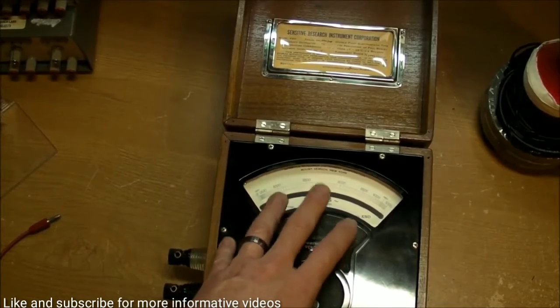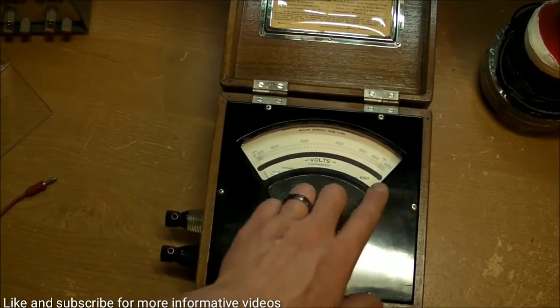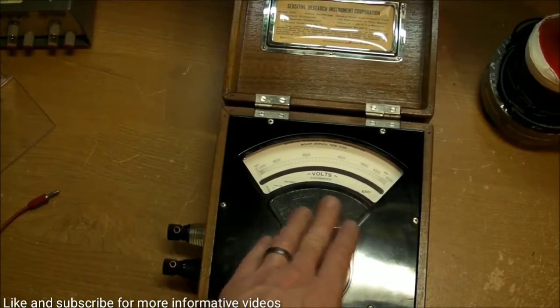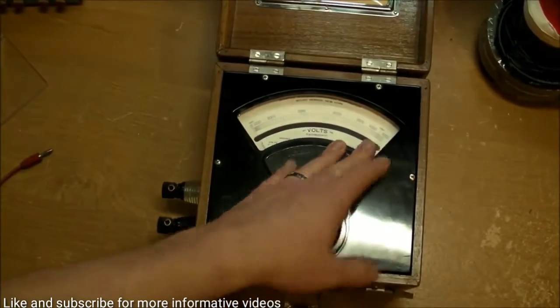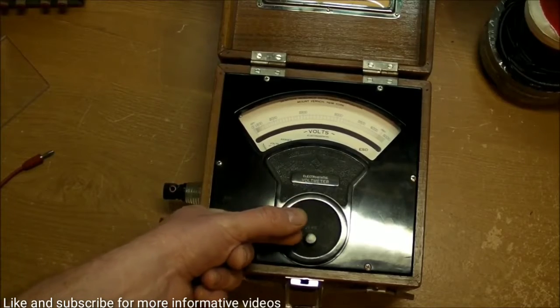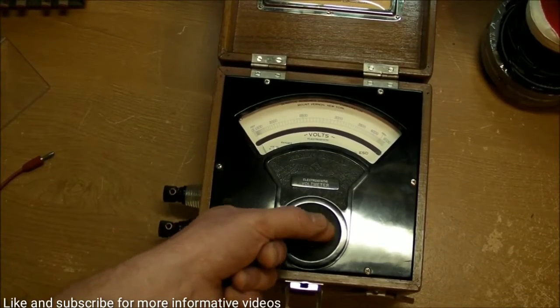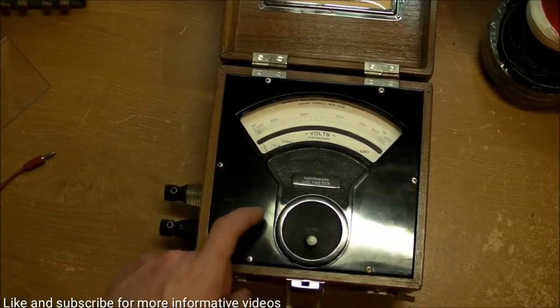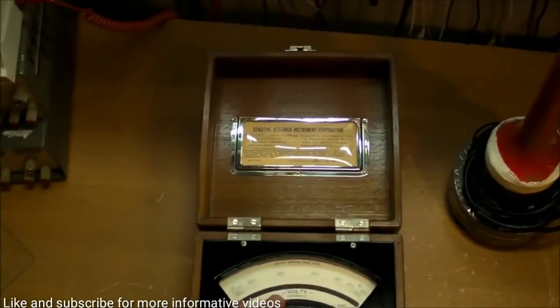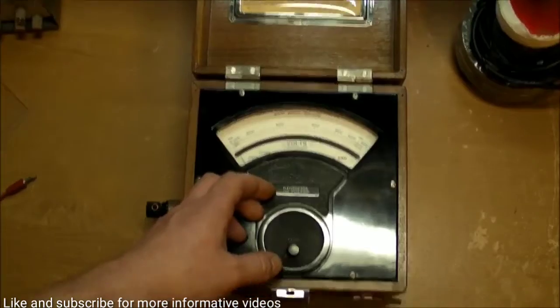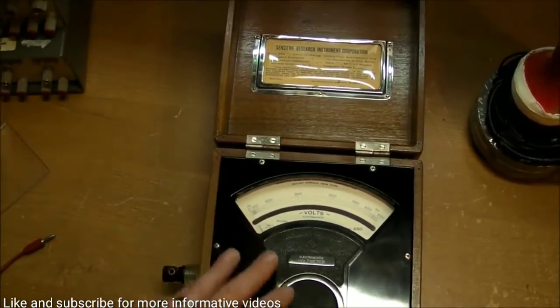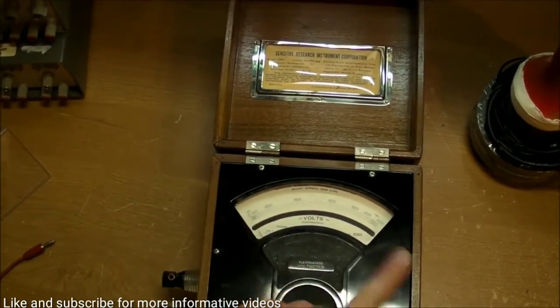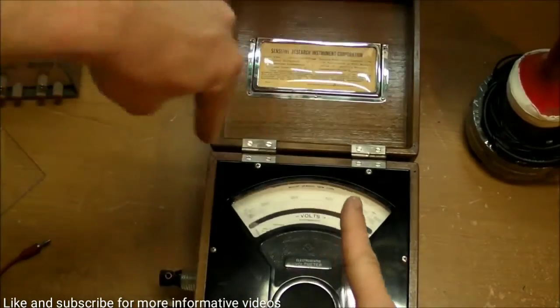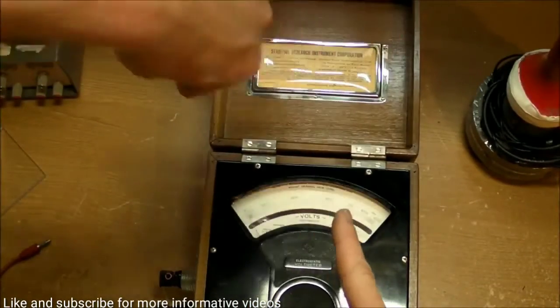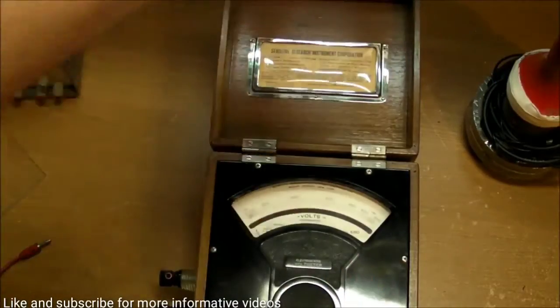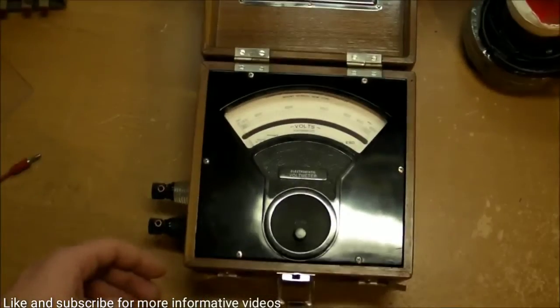Not this particular type, though. I saw one that went down as low as 300 volts. So instead of 5 kilovolts, it was a 300 volt full scale. And of course, that's going to have plates on the inside that are much closer to each other, maybe only half a millimeter or so instead of a full centimeter or so that we saw in here. And also they've got higher voltages like 10 kV and 50 kV and various different constructions, where instead of looking down on a needle pointing like this, you'd be looking sideways on a needle that moves in an arc like that. Completely different topologies. Have a look, see what's out there if you really want to get one of these.